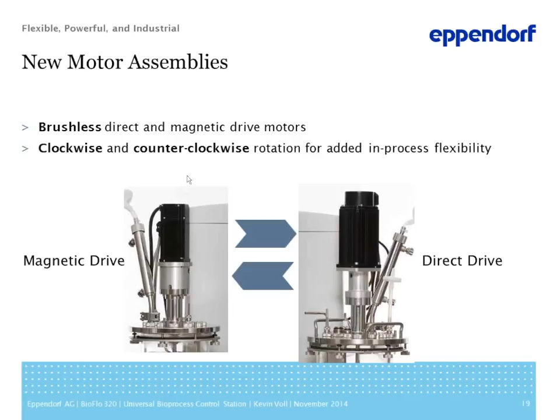You can see the interchangeability of the magnetic direct drive. Within the same vessel, you can be flexible in rotation direction, and you can also be flexible between magnetic and direct drive. Just to give you an idea of what we offer, our direct drive system has 1 motor with one motor assembly, operating up to 1200 RPM.